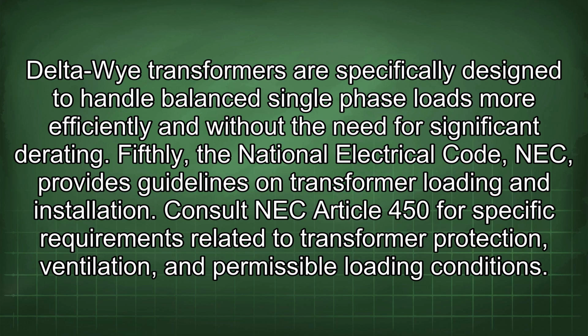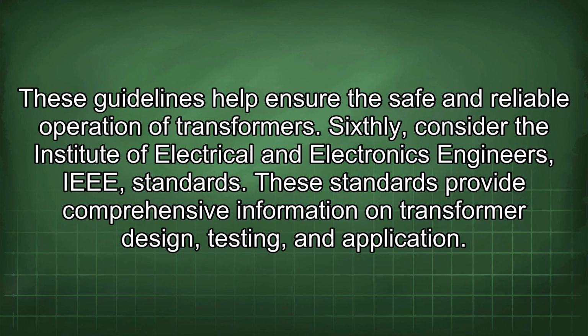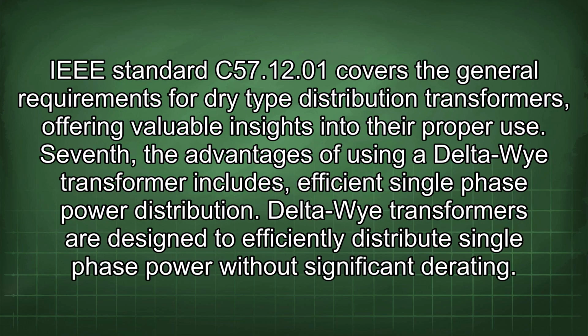Fifthly, the National Electrical Code, NEC, provides guidelines on transformer loading and installation. Consult NEC Article 450 for specific requirements related to transformer protection, ventilation, and permissible loading conditions. These guidelines help ensure the safe and reliable operation of transformers. Sixthly, consider the Institute of Electrical and Electronics Engineers (IEEE) standards. These standards provide comprehensive information on transformer design, testing, and application. IEEE Standard C57.12.01 covers the general requirements for dry-type distribution transformers, offering valuable insights into their proper use.